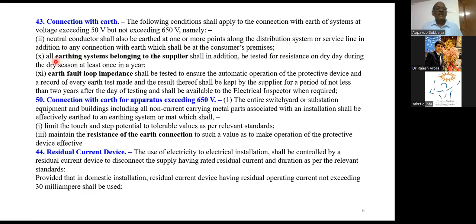Another thing, all the earthing systems belonging to a supplier should be tested for resistance. Here only the resistance comes into the picture. Previously people were using the terms invariably, they measure the earth resistance value of every earth electrode. The auditors coming into the picture are demanding earth electrode resistance. It has become a very popular saying from the auditors. So actually, additionalities and clarity: the standards have now prescribed that the earthing system belonging to the supplier shall be tested.